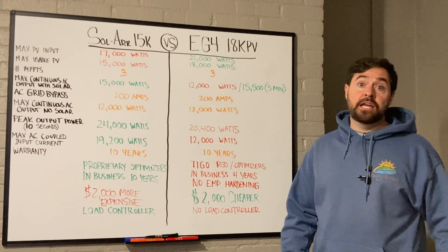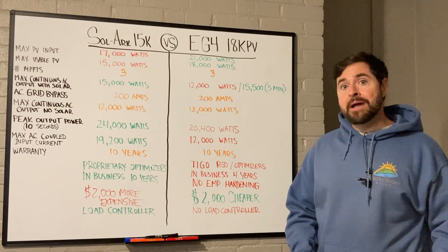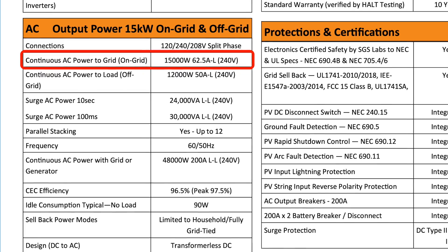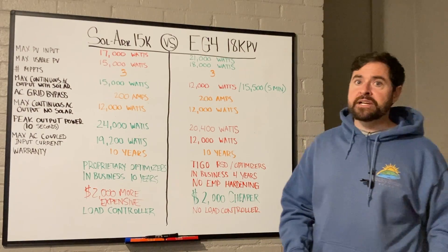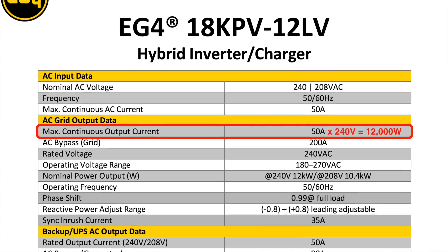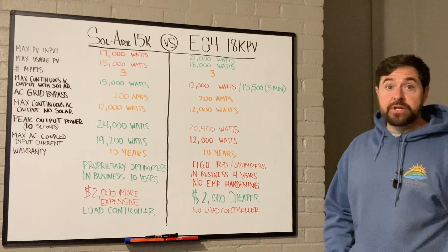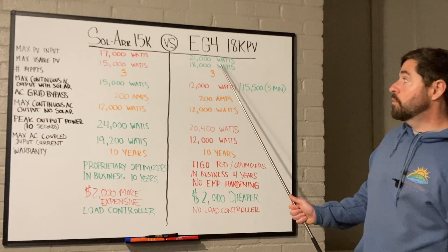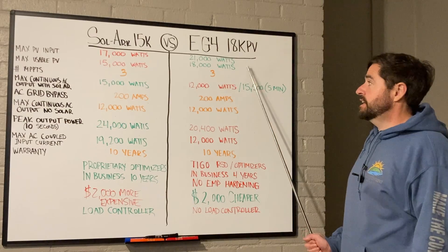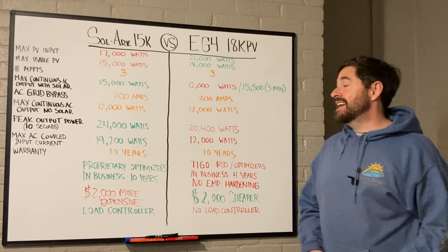Don't let the EG4 18K PV name fool you — it's a little misleading. Most inverters are named on their max continuous output current. A Sol-Ark 15K has 15,000 watts of max continuous output — that's standard in the industry. But EG4 only actually has 12,000 watts max continuous output, so in grid-type standards this inverter should really be called the EG4 12K PV. The 18K PV name comes from the max usable PV wattage, which is 18,000 watts.